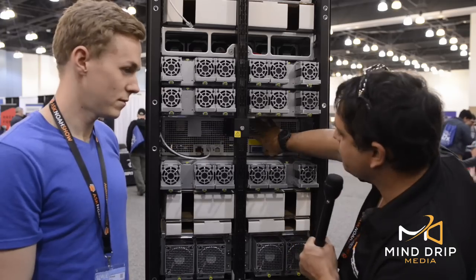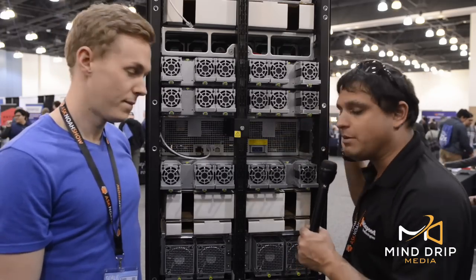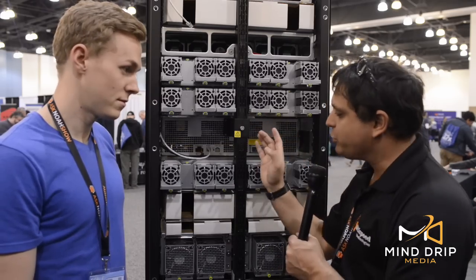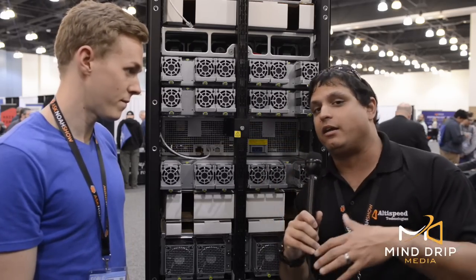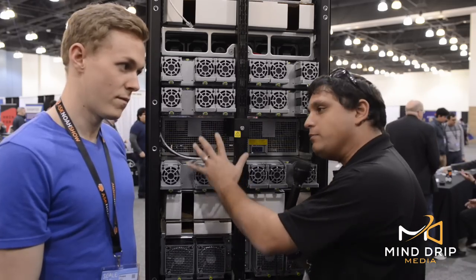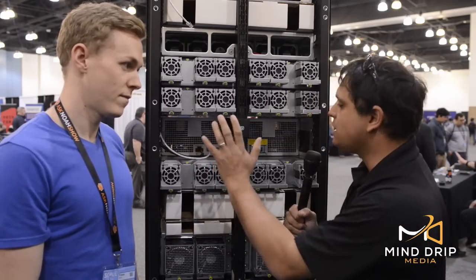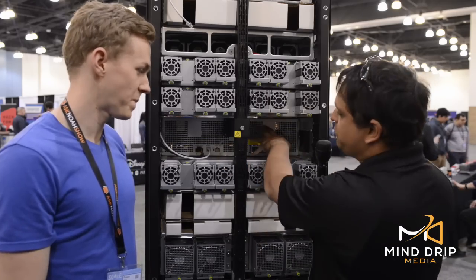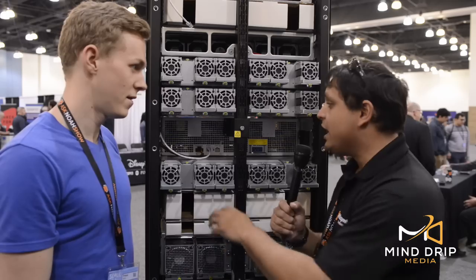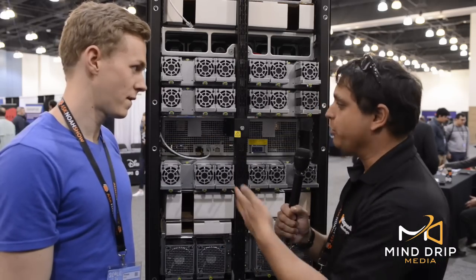So this power supply unit, which actually contains also the battery backup for the UPS, is supplying DC power to the rack, which eliminates a lot of the power inefficiencies that you'd have in a traditional rack because you're not converting from AC back to DC, back to AC, back to DC as we get into the components. All the components in the rack are going to be DC. The backplane of the rack is DC, and so we just make that conversion once as we take AC power in, convert it to DC, as well as provide the DC power for the battery backup.